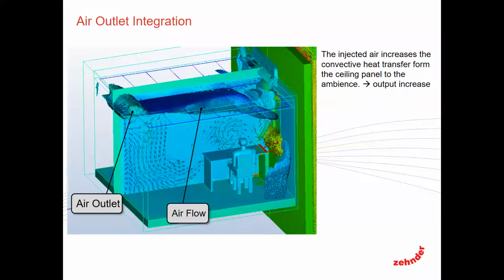One of the other sides of this is air outlet integration. I'll see a lot of diffusers, or even more popular nowadays, I've seen a number of installations with ceiling fans. Mounting those fans and creating a convective flow below the ceiling panels themselves increases that convective factor across the panels. Now you're not derating them, you're actually adding additional capacity to them. So you're adding that extra capacity, so you now have, again, another safety factor, knowing that you're going to get that in the actual space itself.